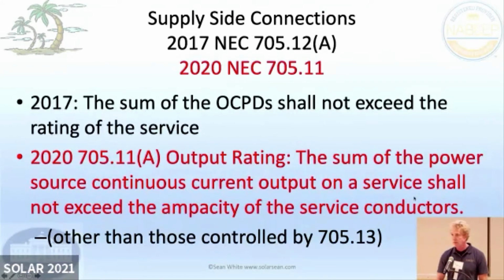We've got a big supply there, but utilities get close to the edge. So why can't we? They'll actually put more current on a wire than the NEC says it can carry, but that's because the utility doesn't have to follow the NEC. They can do whatever they want, or they follow the National Electrical Safety Code. Some people say that what the utility uses for overcurrent protection is a lot of times aluminum conductors, and the aluminum will just melt. There you go, that's real safe. I wouldn't want to be standing under that conductor while that happens. I hate getting aluminum showers. There's other things too, though. And it says, and other than those currents controlled by 705.13.